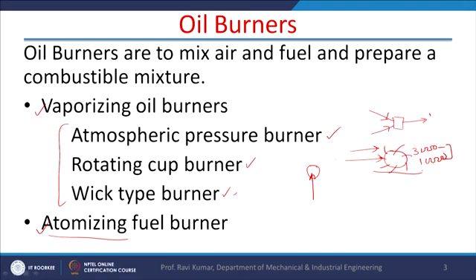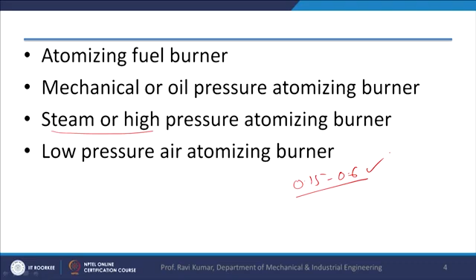Now there are atomizing fuel burners also. In atomizing fuel burners, there are mechanical or oil pressure atomizing burners, where the fuel is injected in a pool of air with a very high pressure. So atomization of fuel takes place, and this mixture is sent for burning. In another type, high pressure steam is mixed with the fuel, and then the mixture is injected for burning. There are low pressure air atomizing burners also for special applications, and the pressure may be around 0.15 to 0.6 bar. They are used in some specific applications.